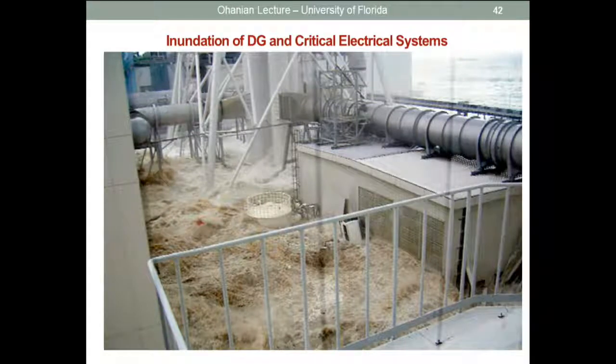Now picture yourself in the control room at this point in time. Obviously, you don't have picture windows in control rooms. They're protected from the outside. Now all of the electrical switchgear is underwater. You've lost all of your AC power, either because of the earthquake, which is a 9.0 Richter scale earthquake, one of the largest ever recorded. They have no off-site power. They flood their DC batteries, which are supposed to last for 8 hours.